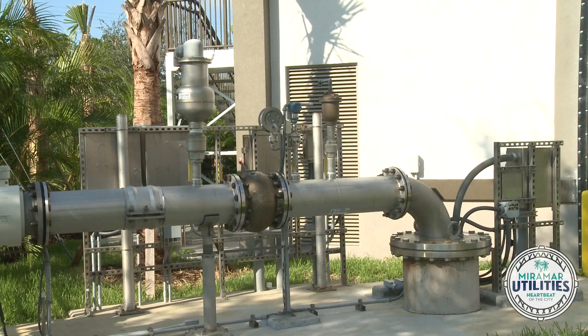This plant was originally designed and built in 1955 as a lime softening plant. It lasted many years, but finally reached its lifetime, and we've replaced it with a nanofiltration plant. We take 80% of the water out of the water stream and leave all the minerals behind with the last 20%, called our reject, which we put down an injection well 3,600 feet in the ground. The water is basically fresh water with a lot of minerals in it, and we're putting it into a zone where the water is brackish, slightly salty. This way, in the future we might be able to draw that water back when the technology is available and use it for drinking water too. So the technology we're using now is setting us up for the future, and as technologies improve the treatment process, we'll be able to work toward that.